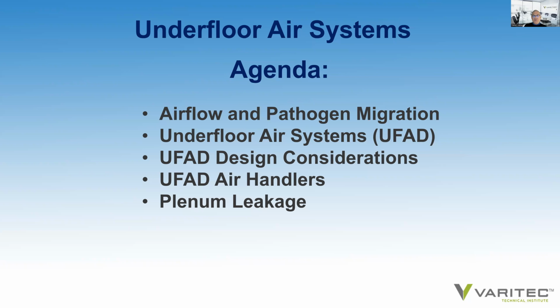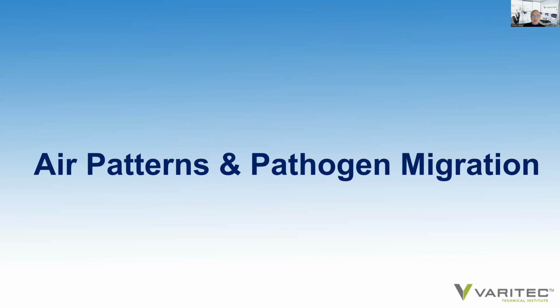Then we're going to look at underfloor air systems. We're going to look at UFAD design considerations and strategies. We're going to look at UFAD air handlers and how they are currently being designed and laid out to reduce the mechanical footprint in buildings. And then we're going to look at the biggest nemesis of UFAD applications, plenum leakage, what to look for in plenums, and how a manufacturer's rep should be able to support a project to minimize leakage to create successful UFAD installations.